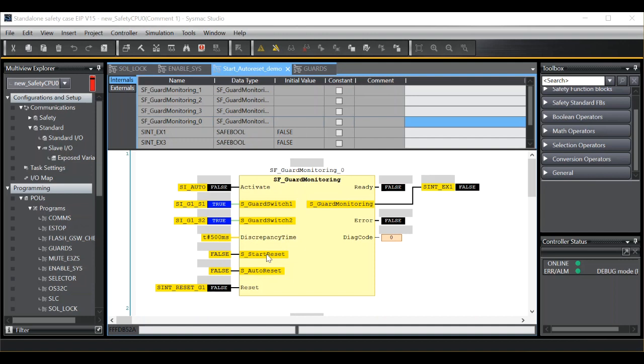Start reset is the reset condition requirement as the function block is activated if we have a logic condition of one on the safety function input variable, in my example a guard switch. Upon transition of the activate variable moving from false to true, it denotes how the function block should respond.